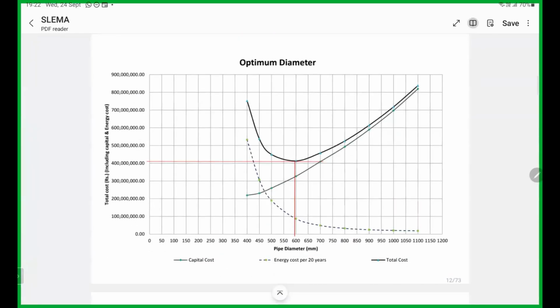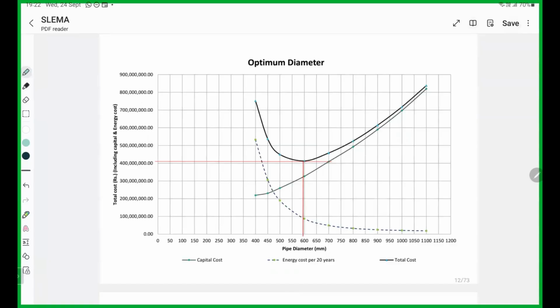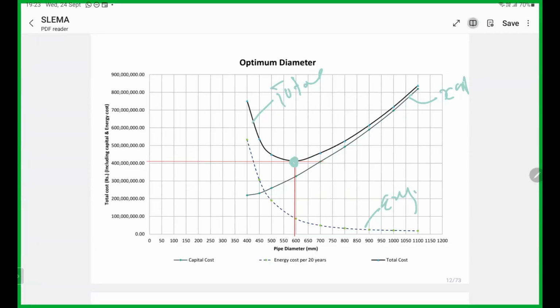Then generally what we do is we calculate, say, this is capital cost, then this is energy cost, this is the total cost. Then we have a curve shape like this. Then we have the optimum pipe diameter, and you can select the optimum pipe diameter using this. I can share this Excel sheet if you want. Then you can calculate everything: energy cost in pumping system, pipe diameter and selection, right? Then we have the Excel sheet.